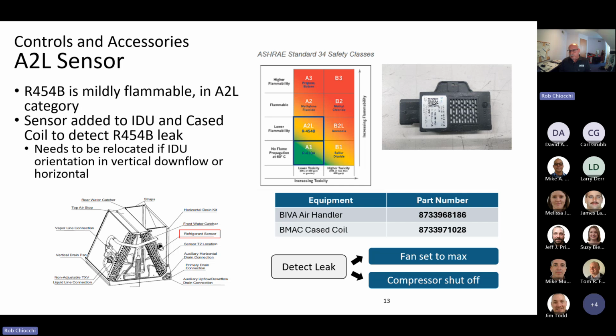One of the changes, though, with the transition to A2L is the incorporation of the leak detection system all manufacturers are required to have on their systems with a charge level of over 4 pounds. So if the system has more than 4 pounds of refrigerant, or the capability of more than 4 pounds of refrigerant, an A2L leak sensor must be incorporated into the system. This sensor will be pre-installed on all the coils and all the air handlers moving forward.